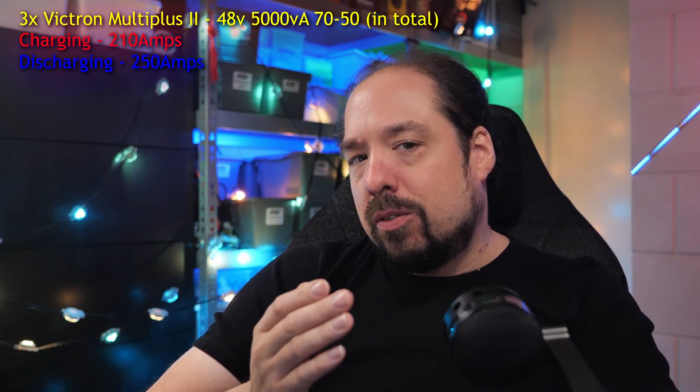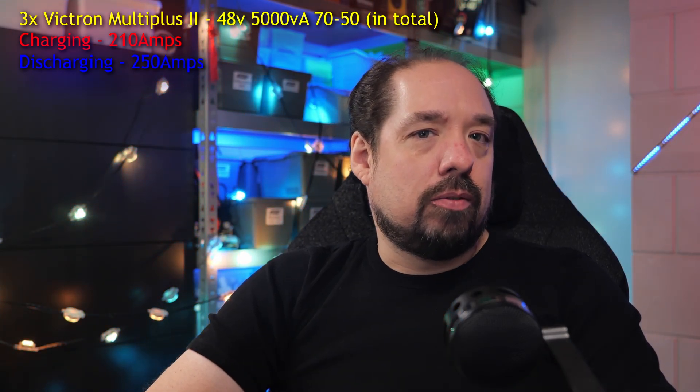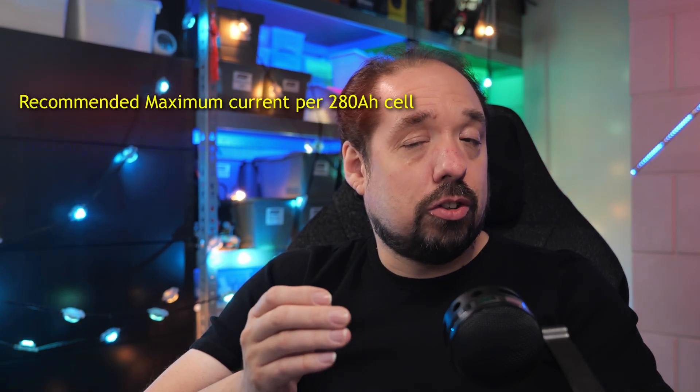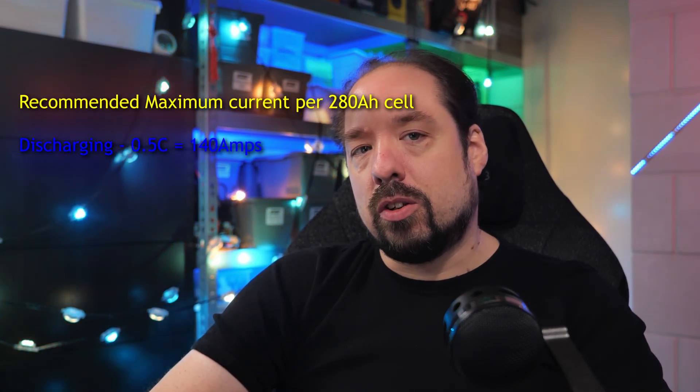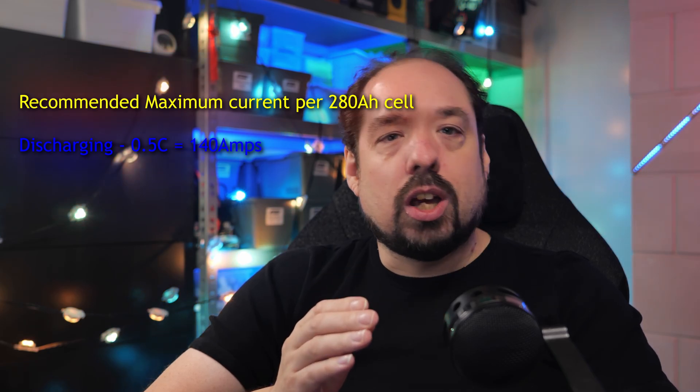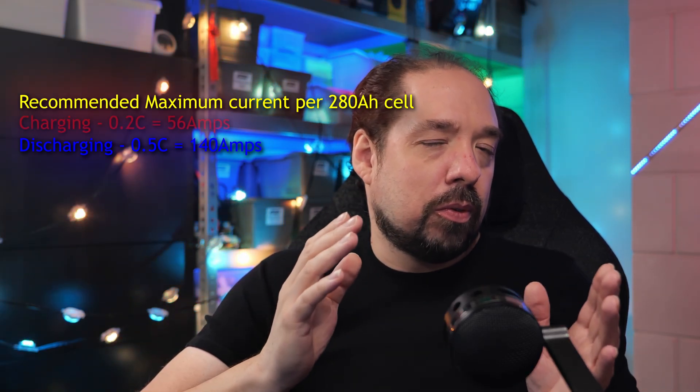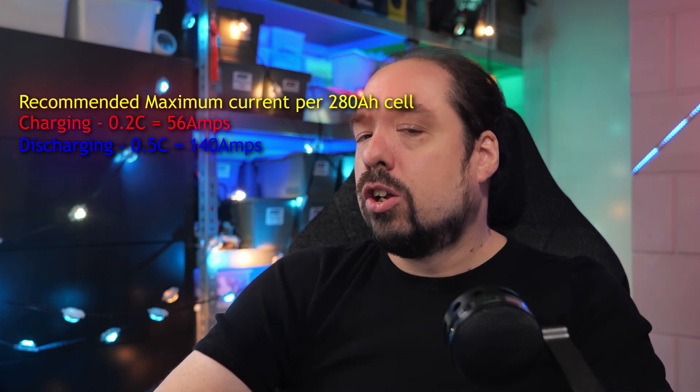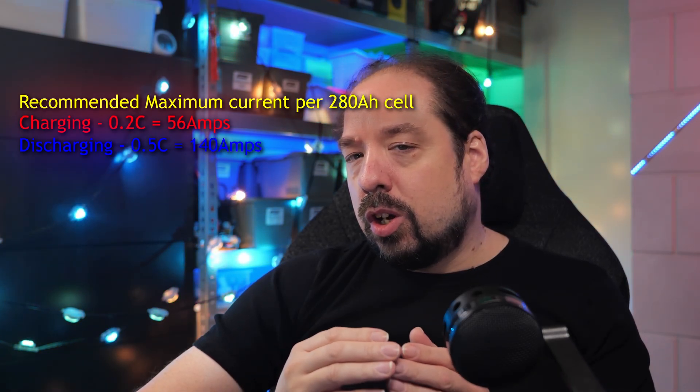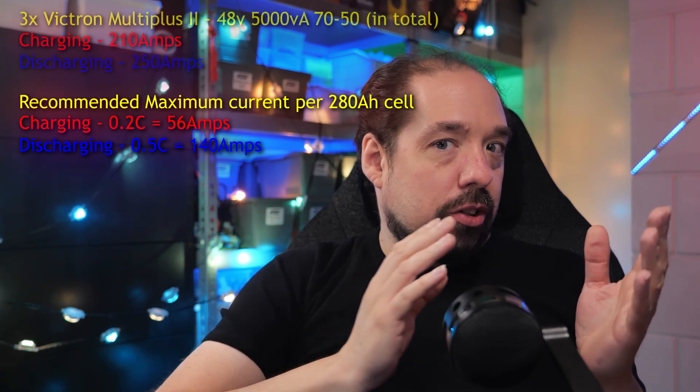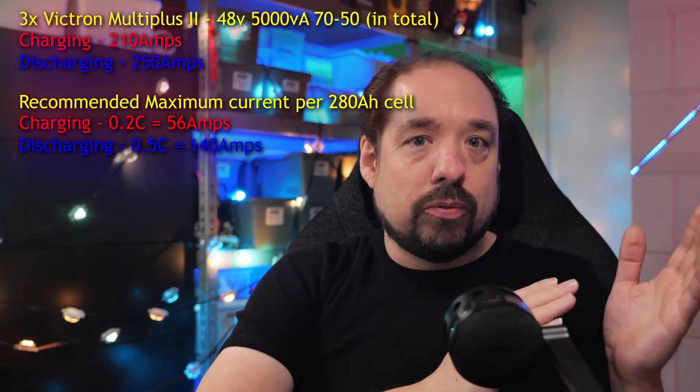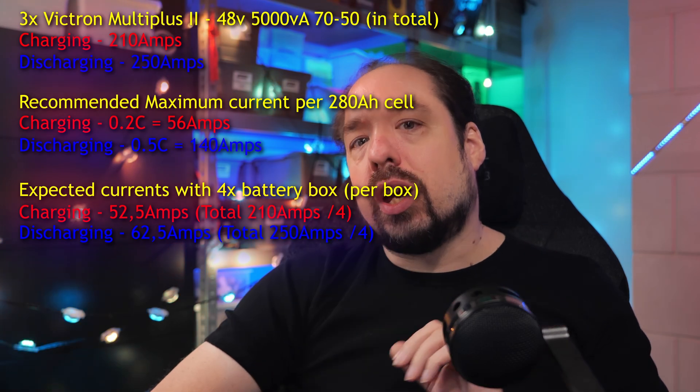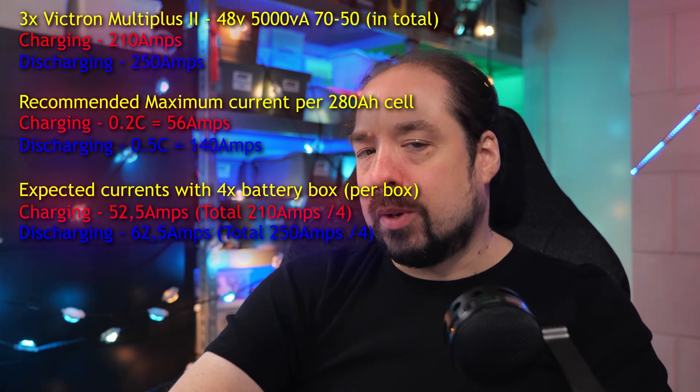These batteries or LiFePO4 cells have a rule that you don't want to discharge them at more than 0.5C, so in the case of a 280 amp hour cell, that is 140 amps, and preferably charge them with about a maximum of 0.2C, so 56 amps. That would mean a way overloaded current for a single battery box, but with four of them, they will all share this load, and we have an almost perfect match.